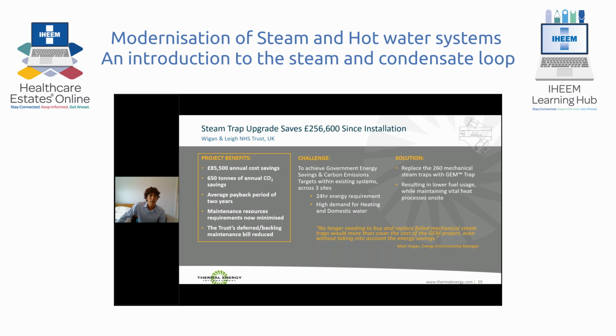Here we have an example of a case study, again at the Wigan and Leigh Hospital. They replaced 260 mechanical steam traps, saving £85,500 per year. One of the biggest advantages that Mark Hogan, the environmental manager, saw was the elimination of the requirement of spare parts and replacement traps and the associated maintenance costs.